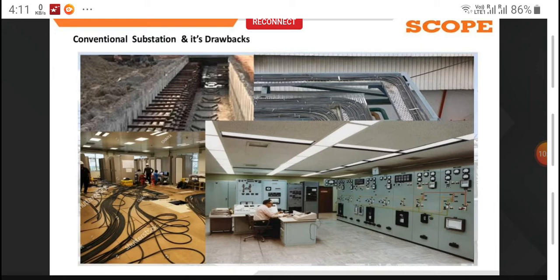When you go to the transmission segment, you have a lot of substations which are almost SCADA-based. When it comes to the distribution segment, the problem is that around 80% or 90%, I can say, are conventional substations where there is no SCADA. And the new substations coming up in distribution are going to have a substation automation system from the initial stage itself.